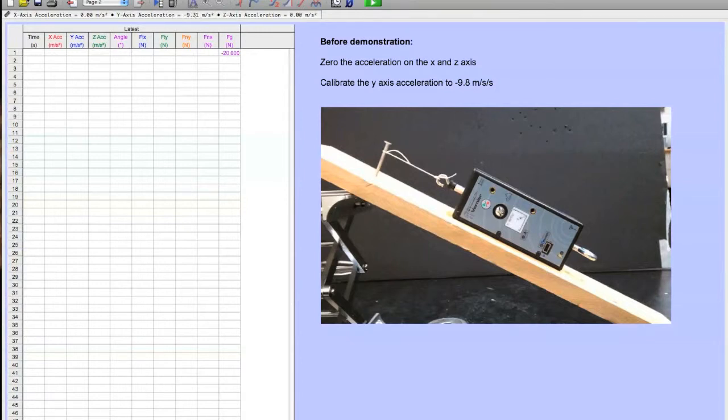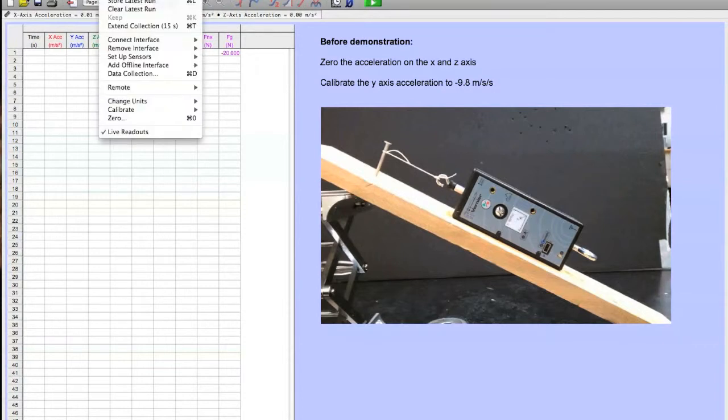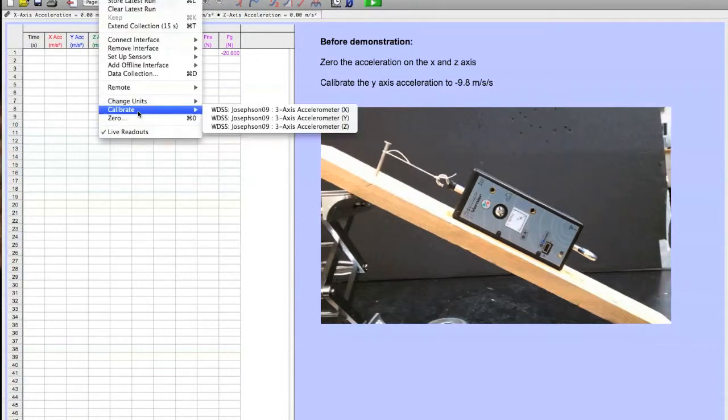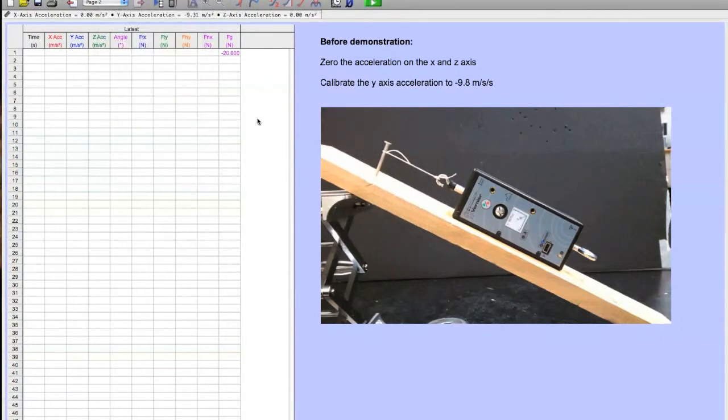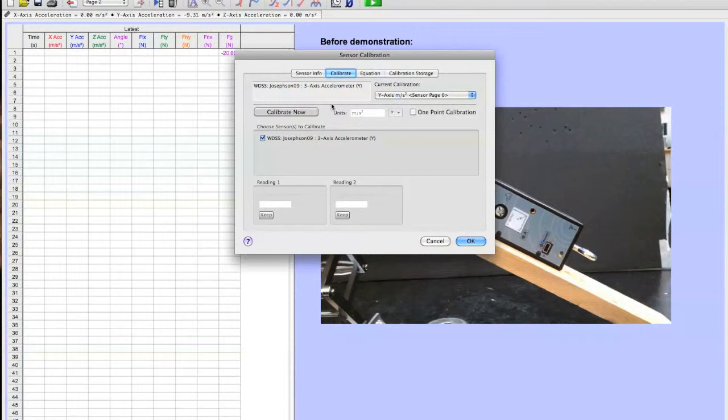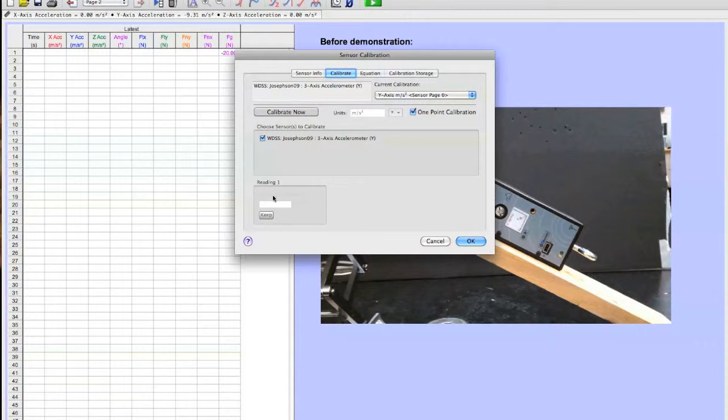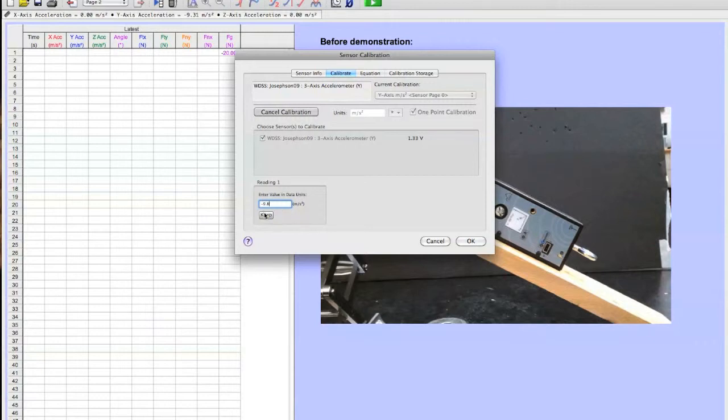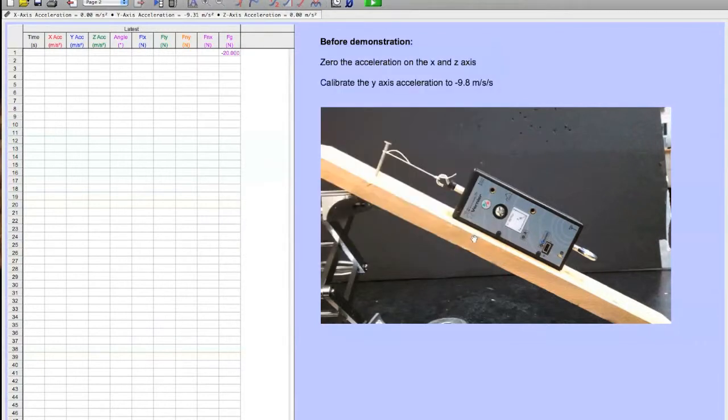so I want to go in and adjust that. That can simply be done by experiment, calibrate, go to Y. This is going to be a one point calibration, so you check the one point calibration, click calibrate now, and then type in the negative 9.8. And then don't forget to click keep, I always forget that, and then click OK. And now this clicks over to negative 9.8 and everything should be ready to go.